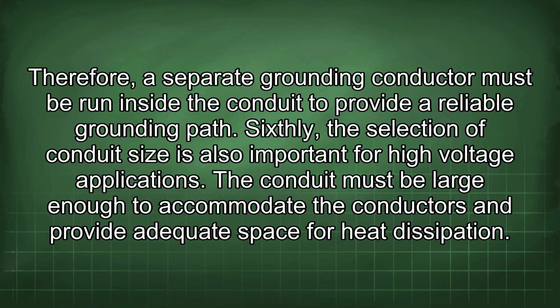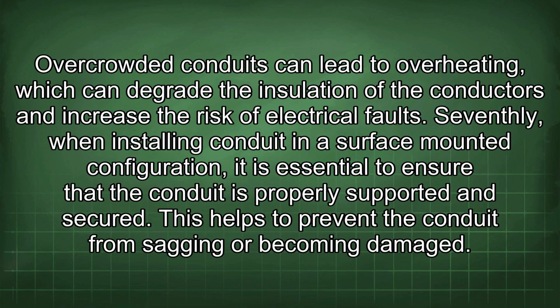Sixthly, the selection of conduit size is also important for high-voltage applications. The conduit must be large enough to accommodate the conductors and provide adequate space for heat dissipation. Overcrowded conduits can lead to overheating, which can degrade the insulation of the conductors and increase the risk of electrical faults.